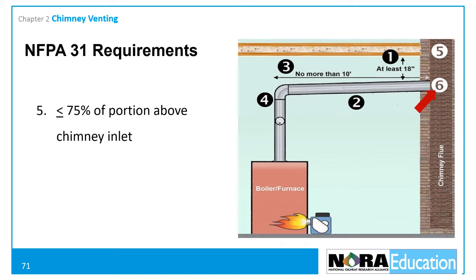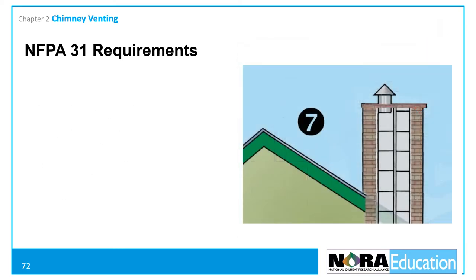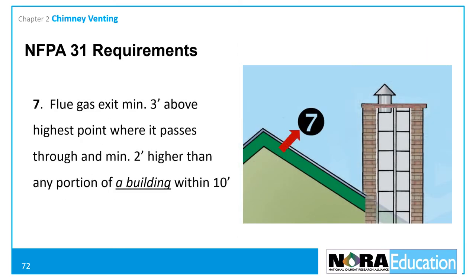Additionally, the flue pipe must not be longer than 75% of the portion of the chimney above the chimney inlet. For example, if the chimney extends 20 feet above where the flue pipe connects, the flue pipe can be no longer than 15 feet. In masonry chimneys, the flue pipe must extend through the chimney wall to the inner face or liner, but not beyond, and shall be firmly cemented in place. The flue gas exit of the chimney must be at least three feet above the highest point where it passes through the roof, and at least two feet higher than any portion of a building within 10 feet of the chimney.